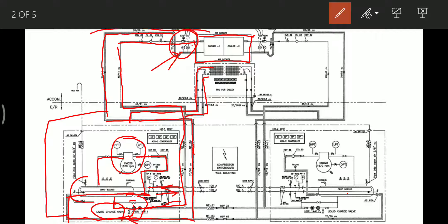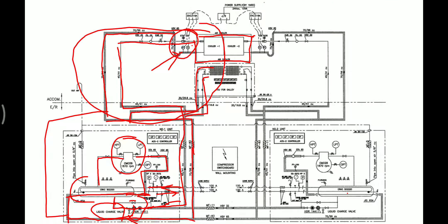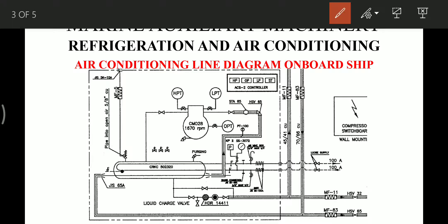Now let's look at each part separately. The compressor has a low pressure transmitter, a high pressure transmitter, and an oil pressure transmitter. There is an oil separator, though it is not shown in this diagram. There is also an oil charging connection for the compressor. The solenoids shown are for loading and unloading the compressor depending on the cooling load on the system.